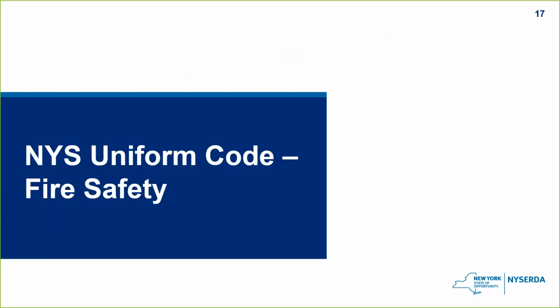Also, as part of this process, when the batteries are overheating, they can begin to off-gas potentially explosive gases. So if those gases are allowed to accumulate in a space, they can present an explosion hazard. And so we're going to spend the rest of the time discussing what is being done to mitigate these risks, both through prevention with stringent, appropriate codes, and also through smart, informed incident response procedures.